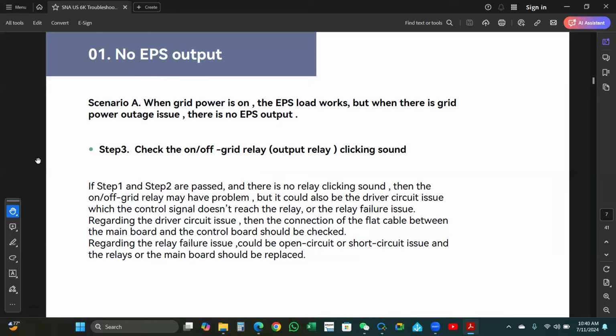Same, no EPS output. Step three is check the on and off grid relay output for clicking sounds. If step one and step two are passed and there is no relay clicking sound, then the on and off relay may have a problem. But it could also be a driver circuit issue, where the control signal doesn't reach the relay, or a relay failure issue. Regarding the driver circuit issue, the connection of the flat cable between the main board and the control board should be checked. Regarding the relay failure issue, it could be an open circuit or a short circuit issue, and the relay or the main board should be replaced.